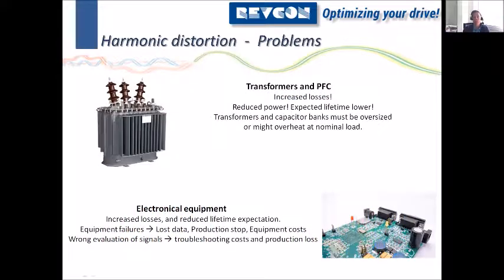Okay, so what other loads and what other problems do we see? I think I mentioned transformers before. They not only suffer from high harmonics, they suffer from all harmonics. But in particular, the high harmonics are locked into the transformer and will heat up the transformer, or the oil, or whatever is installed inside the transformer. So that's one reason to keep an eye on this. And of course, even though the transformer is not overloaded, this will significantly reduce the lifetime of the transformer.